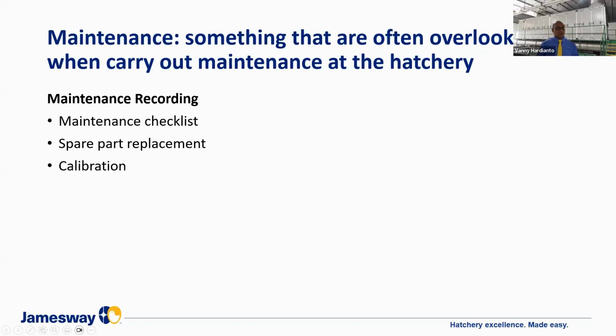And one more thing is the calibration recording. You will easily decide to continue using the sensors, or whether you have to replace the sensor, by checking the history of calibration. When the offset is going very high, it indicates that you need to replace the sensor.